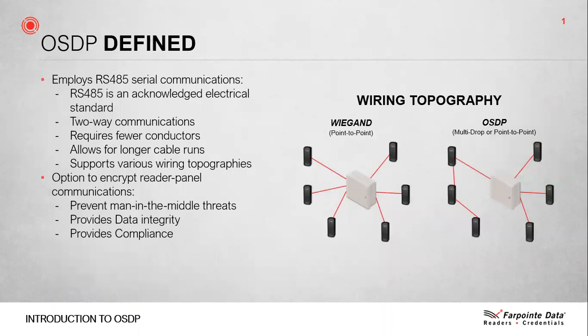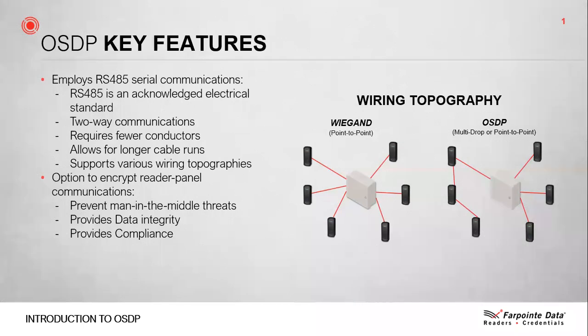Key features. OSDP is built on the RS-485 serial transmission standard. RS-485 is the physical layer specifying the actual electrical characteristics of the signal being generated and received. We like to think of OSDP communications as writing on this RS-485 physical layer. The key advantages here are that RS-485 requires just four conductors — two for power and two for data. For example, a Belden 8723 cable might be something you would use. RS-485 also provides for longer cable runs between devices, often up to 4,000 feet. Also compared to Wiegand, which offers simple point-to-point topologies, OSDP offers point-to-point and multi-drop. Multi-drop will require the individual addressing or naming of the readers within a system.